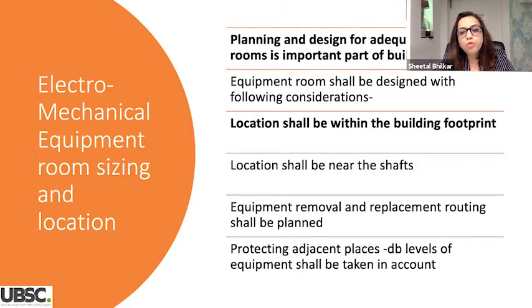If you want to remove a panel, or a DG set, and you have not thought of it, it becomes very difficult from a maintenance point of view. So everything should be planned in the beginning, when you are placing that equipment. And whenever you are placing these electromechanical rooms, you should also think about the dB level. Suppose you are placing it near an auditorium, it is not advisable, because if a DG set or some fan is there, that noise will be there. So you have to think of all these aspects when you are locating these rooms.